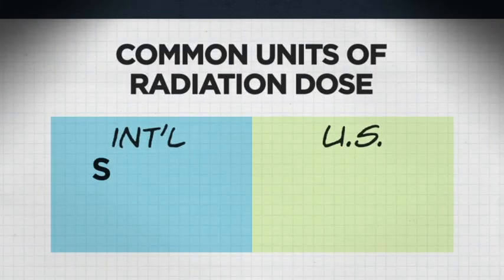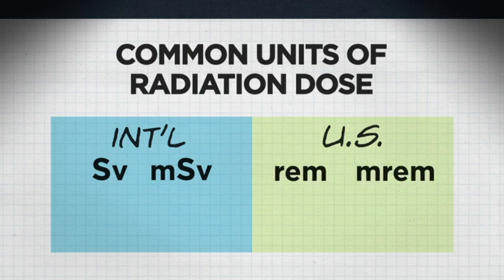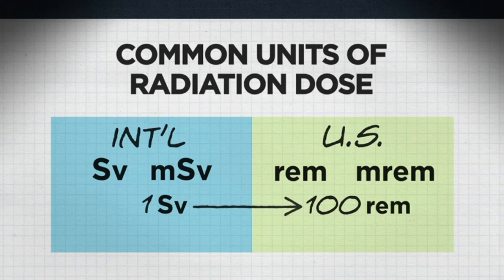We express ambient radiation levels per hour. For example, if radiation levels are one millisievert per hour and I stand there for two hours, I receive approximately two millisieverts of dose. Millisieverts is a common unit — recall that natural background radiation gives us about three millisieverts per year on average. In the United States, we use rem and millirem as dose units. The conversion is simple: one sievert equals 100 rem, and one rem equals 10 millisieverts.